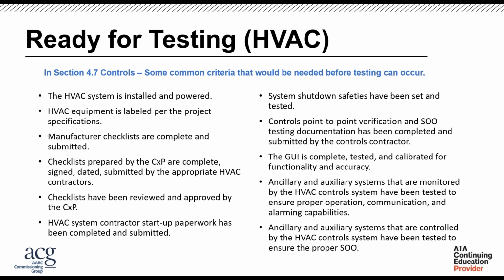And when we're actually testing, not only that the overall manufacturer's control system is set up and started up, but that the building-wide BAS system points are reporting back and actually communicating with each other. A lot of times I've worked on package units that might have a specific manufacturer controller where the overall school's BAS system is just reading that point, turning it on or off.